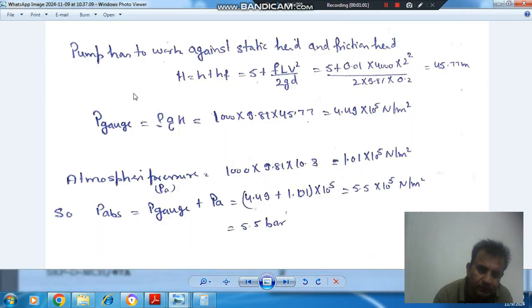So here, pump has to work against static head as well as friction head. So H is Hs plus Hf. Static head is given as 5, and friction head is FLV squared by 2GD, where F is friction factor, L is length, V is velocity, D is diameter.